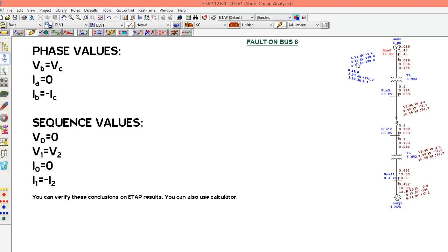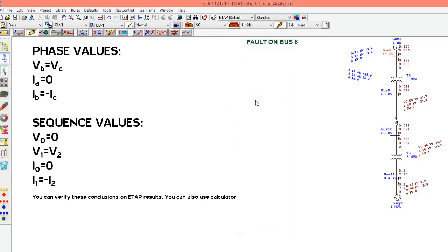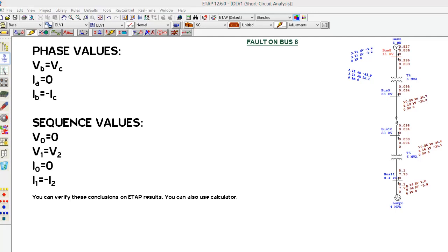We can verify all of our findings here on ETAP. We can see that phase B and phase C voltages are equal in magnitude and in phase. The phase currents are equal in magnitude and opposite in phase. In the sequence values, V0 and I0 are zero. You can use a calculator to verify that V1 equals V2 and I1 equals minus I2.